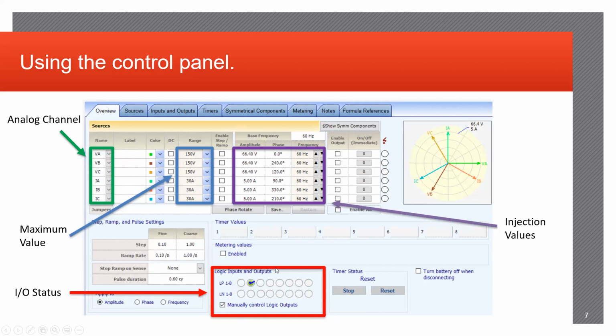In the orange square over here is going to be identified your inputs and outputs from the test set. So another key important factor is identifying that your inputs and outputs that you're going to be utilizing from your test set have been enabled and identified properly, so that you understand which input goes where and that it's actually going to be picked up when testing.